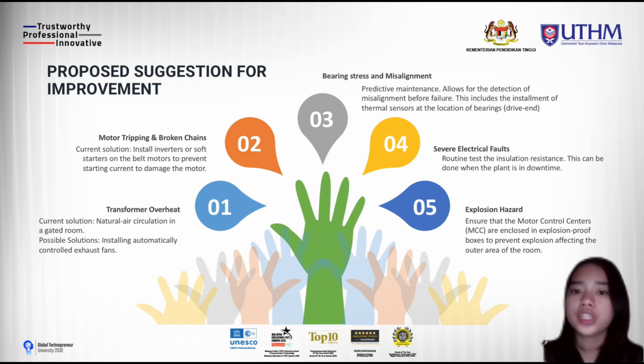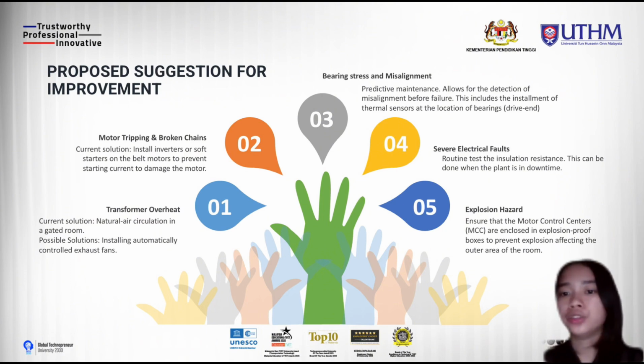The third is bearing stress and misalignment, and one of the ways to overcome this is predictive maintenance. This allows the detection of misalignment before failure. One of the ways is to install thermal temperature sensors at the locations of the bearings. The fourth is severe electrical faults, and one of the ways to overcome this is to do a routine test during the plant's downtime to test the insulation resistance.